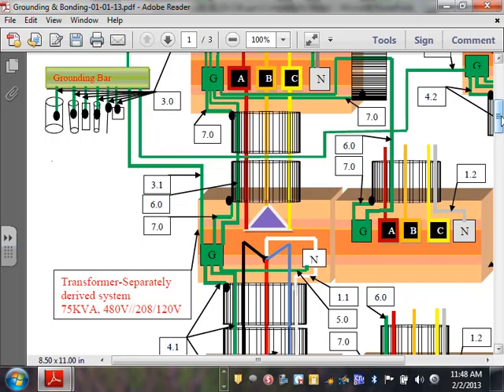And that will, what do you call it, the inter-system bonding. That will meet the requirement of the inter-system bonding terminal that you are supposed to do for bigger systems. For smaller systems it's a tiny little connector. For bigger systems, your telecommunication companies can directly tie. If you have a data center, they use tons of insulated grounding system. They can tie directly to this point.